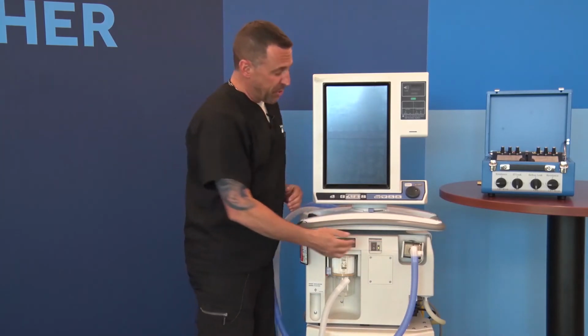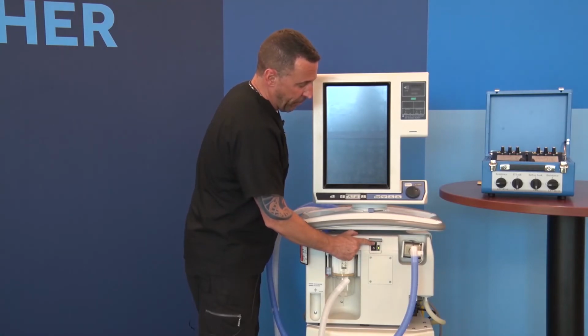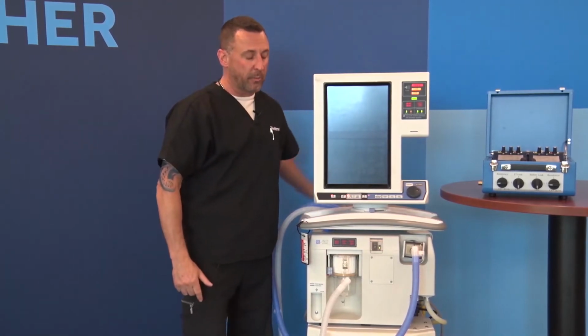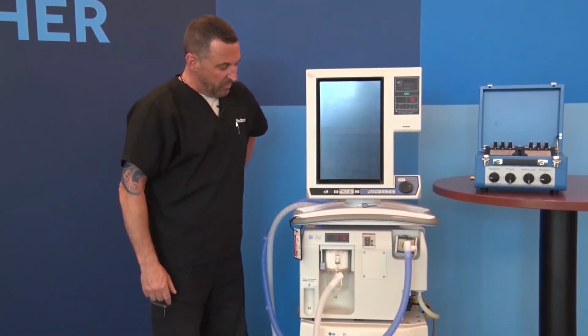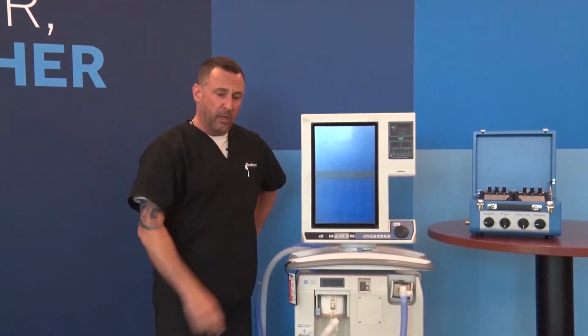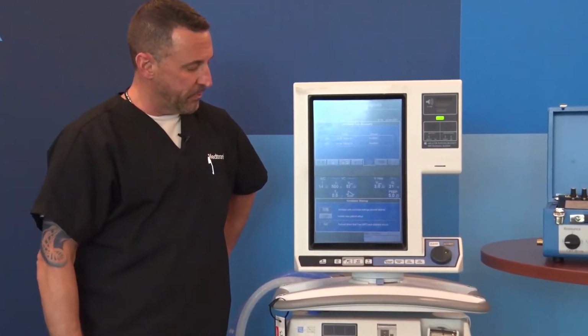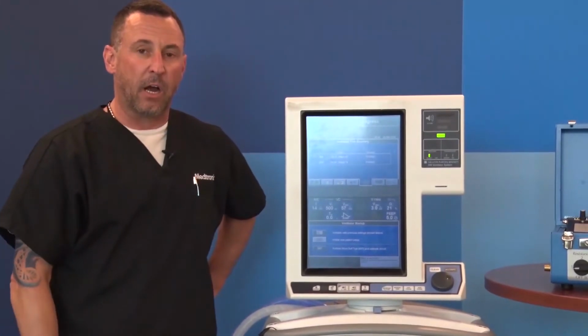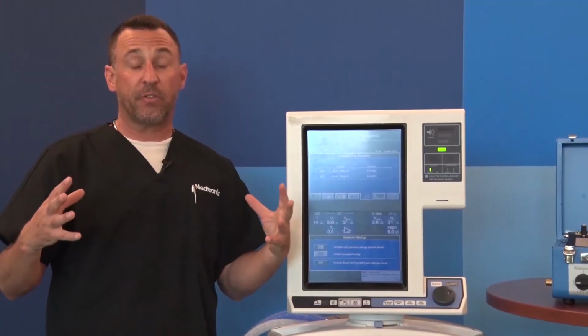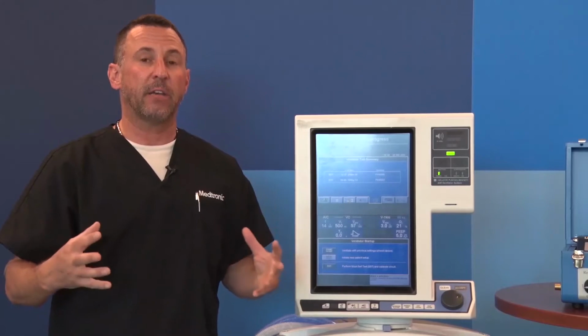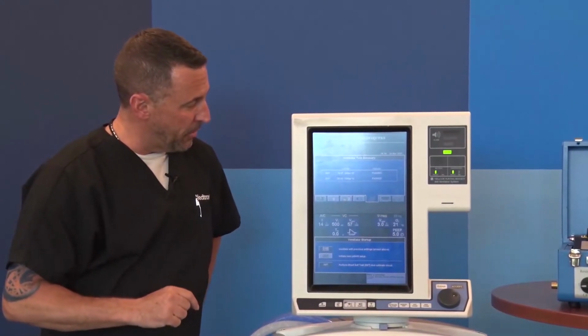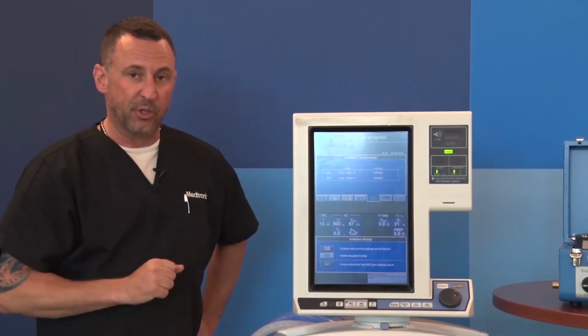I'm going to go ahead and turn the machine on. Power switch is right up front. I'm already plugged in. Gases are already plugged in. The ventilator goes through a short startup procedure here. You hear the compressor kicks on so that it is fully charged with 50 psi of air at any given moment. So that's the noise you just heard. And now you see some information on the screen.